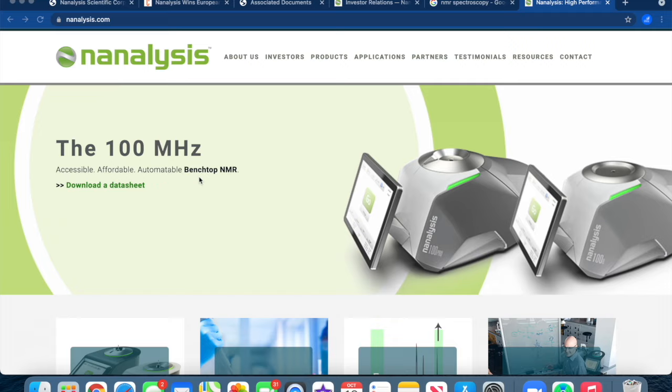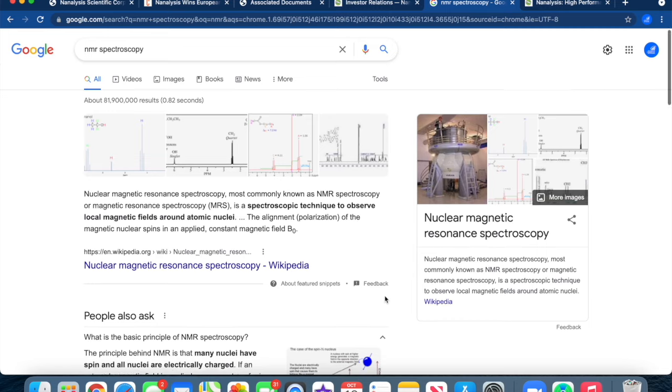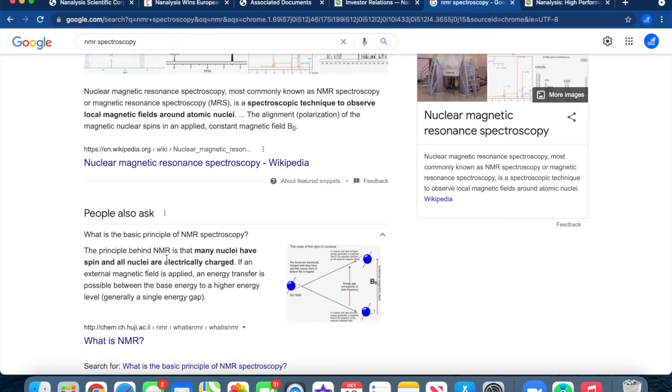Nanalysis has basically developed an accessible, affordable, and automatable benchtop nuclear magnetic resonance spectrometer. The principle behind NMR is that many nuclei have spin and all nuclei are electrically charged. If an external magnetic field is applied, an energy transfer is possible between the base energy to a higher energy level, generally a single energy gap. There's more information you can review on what nuclear magnetic resonance spectroscopy does and the benefits it has in many various industry sectors.